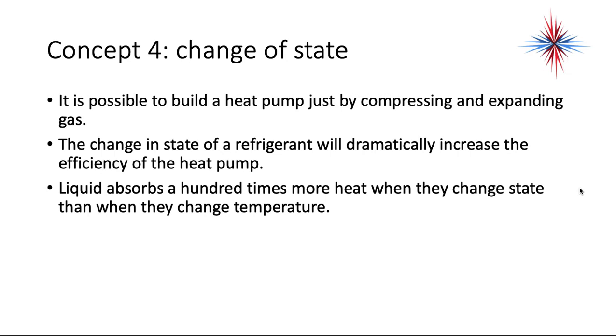Concept number 4, the change of state. In other words, liquid to gas, gas to liquid. It's possible to build a heat pump just by compressing and expanding gas. The change of state of a refrigerant will dramatically increase the efficiency of the heat pump. Liquid absorbs about 100 times more heat when it changes state than when it changes temperature. Remember, change of temperature is sensible heat.